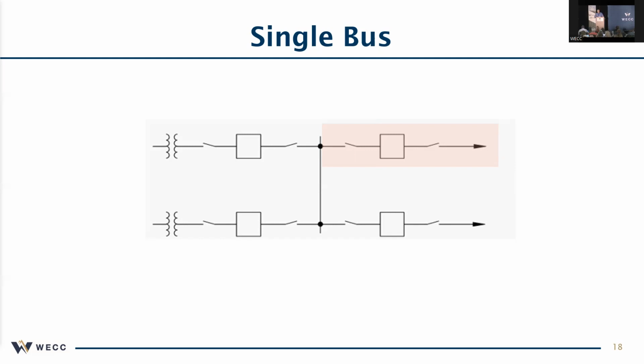But you folks that are doing the facility limits, you should consider all that. You probably do. It's just a matter of, do you document that somewhere? Such as, if an auditor did say, hey, what about this disconnect on the upstream side? Even if you don't consider that in your facility, that's a fair question. Different facility possibly, but you still should have a rating for it. So when you're getting your information together, it's fine to define your facility up through the breaker, but you should also have documentation for those other pieces. That makes that facility absolutely complete in your eyes, and nothing gets missed.